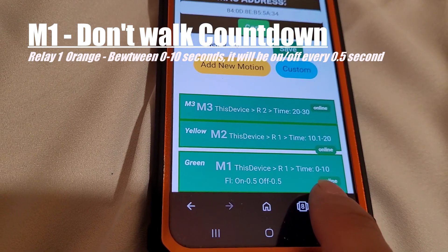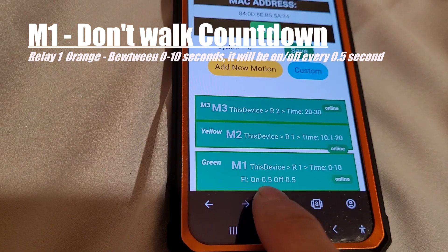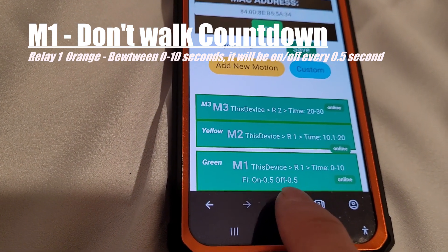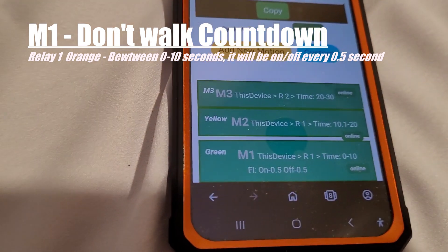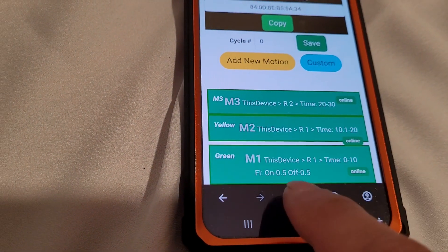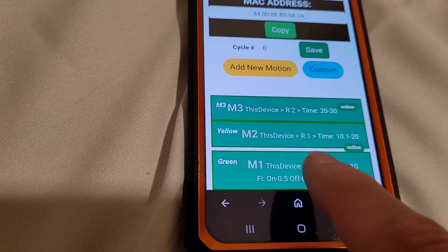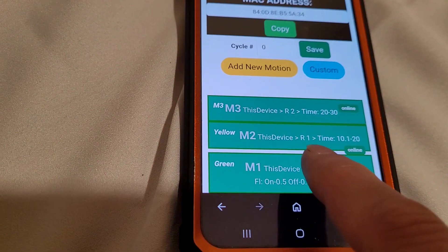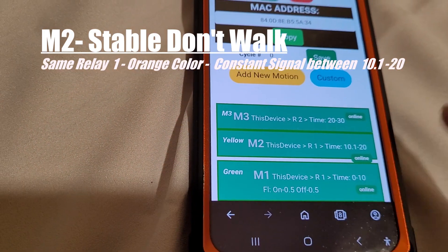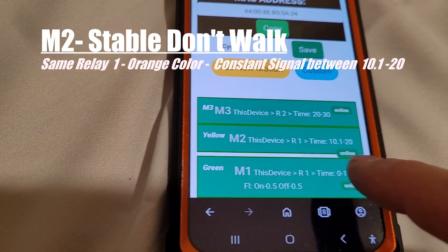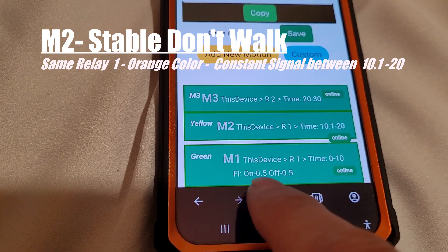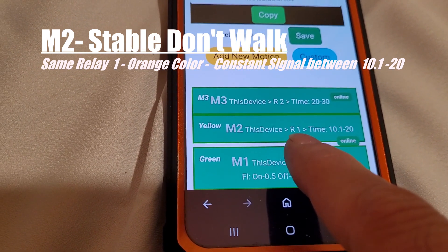Relay one, R1, is for don't walk. From 0 to 10 seconds I am sending a signal of 0.5 on and 0.5 off — on and off repeatedly until it reaches 10 seconds. Next, from 10.1 seconds I send a constant signal with no flashing.